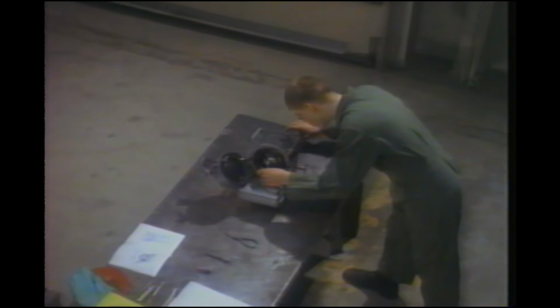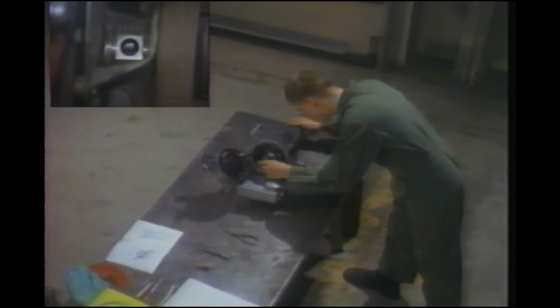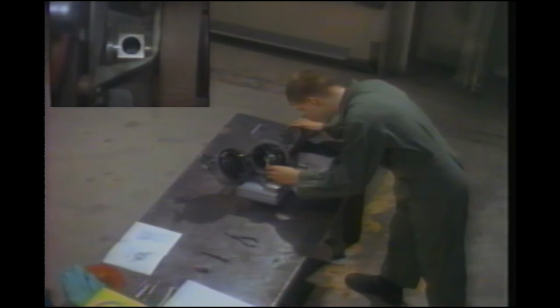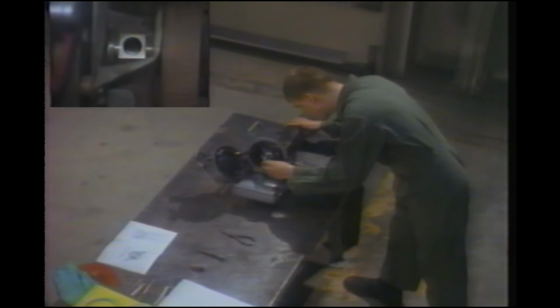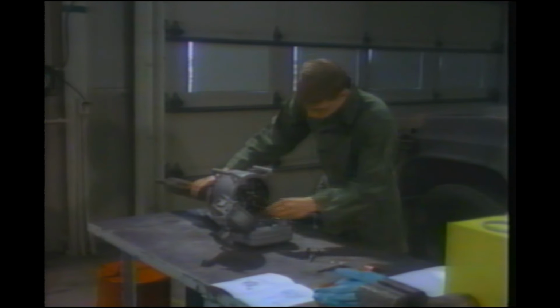Screw the special cleaning rod into the position where you removed the preheating plug from the mixing chamber. Keep turning the rod while moving it back and forth to scrape out carbon deposits. The Swingfire burns clean, so usually there will be very little carbon. You can look into the mixing chamber through the spark plug hole. Remove the cleaning tool and wipe it off.